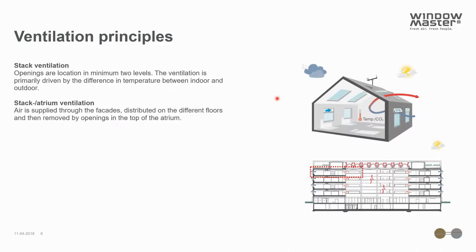The last strategy is of course stack ventilation, which can be perceived in different ways. It will always use thermal buoyancy. In a single zone you will typically have the windows located at different levels and thereby use thermal buoyancy to drive the air and secure a good airflow. But you can also have a building where multiple zones on different levels are sharing the same atrium used for the exhaust of the air. For this type of building it can be more challenging to know which part of the building to use in your air change calculations. We recommend taking a section of the atrium and using the opening area for this part in your calculations, combined with the zone you're investigating.